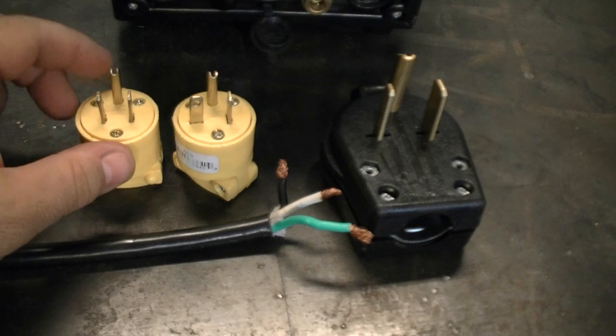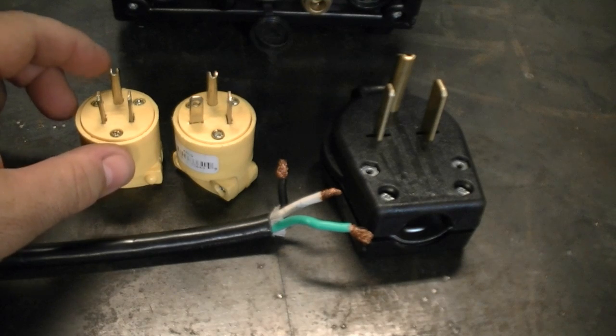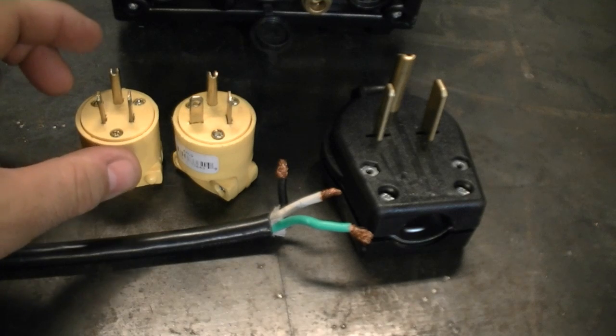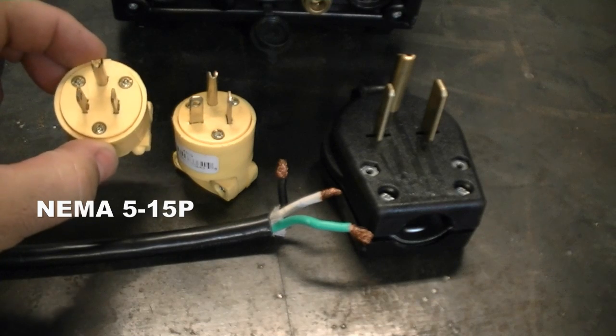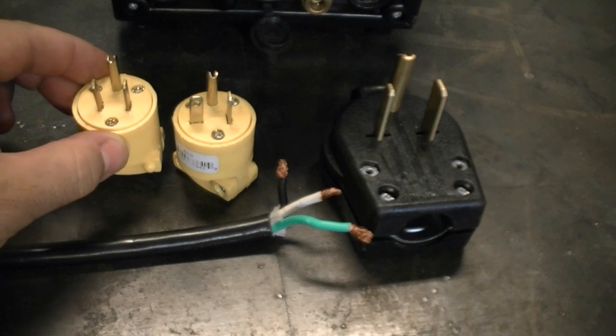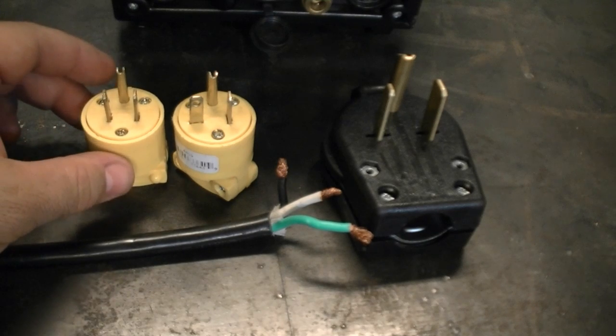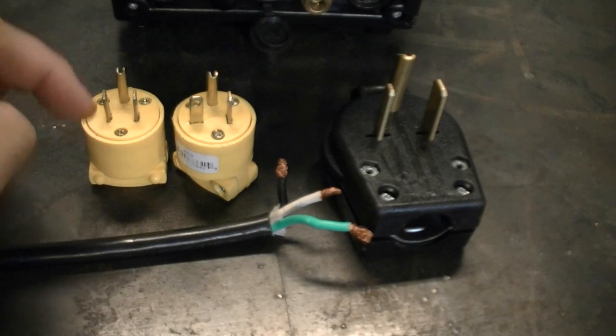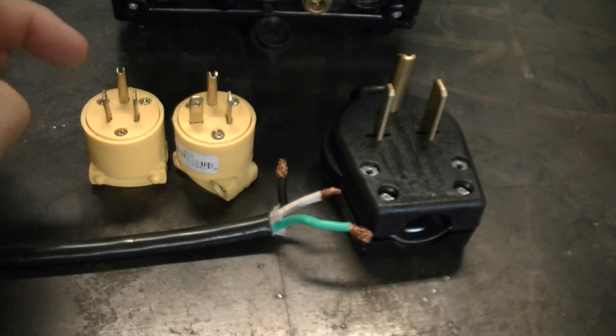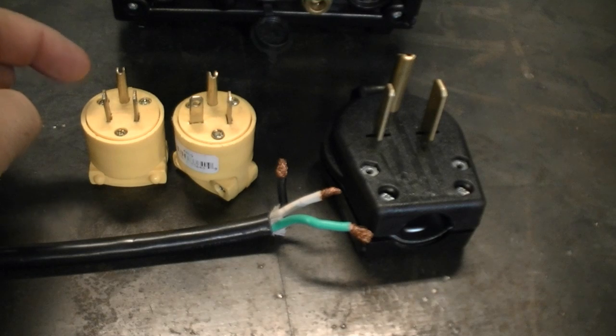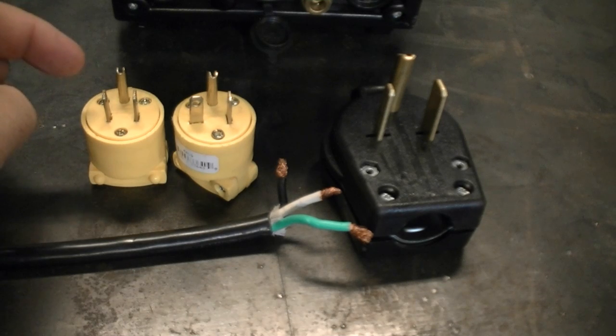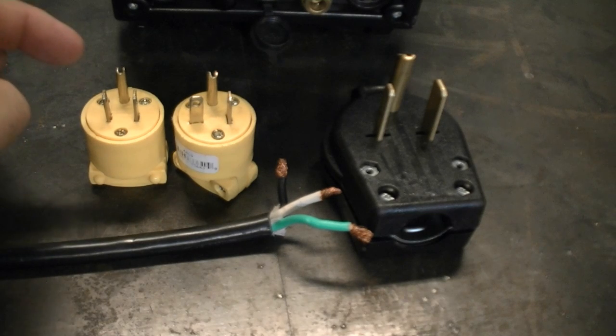This unit is rated up to 20 amps draw on 120 volts. So what you're going to typically look for, for most people, they're going to find that a 15 amp plug will work fine. Now this is your standard plug that you're going to find on a lot of 120 volt welders. Now with that said, the NEC does allow a derating for your wiring and your plug for welding, because it's a duty cycle limited unit. Anytime you have a duty cycle limited unit, you're not putting 100% constant demand on the wiring, so the heat is not as big a factor. Now follow your local codes, because sometimes your local codes override that, and they require a standard type plug in size for the maximum draw of the unit.